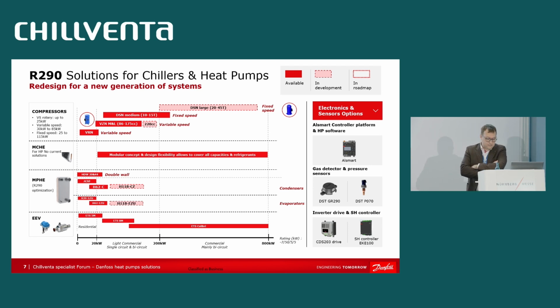Within this controller, we developed a complete application software related to heat pumps. We already have heat pump software running, embedding all the different libraries of our compressors, superheat control, expansion valve control, gas detector control, etc. This has already been embedded and tested within our application development center in Denmark.